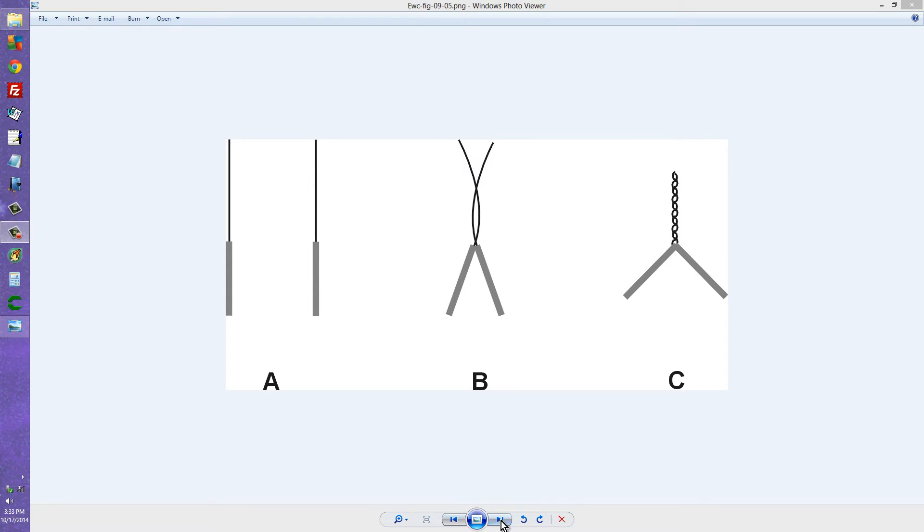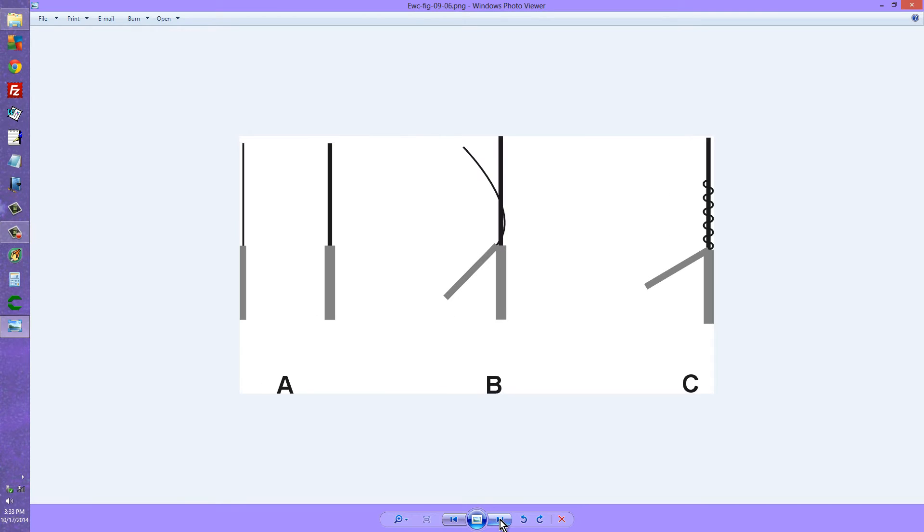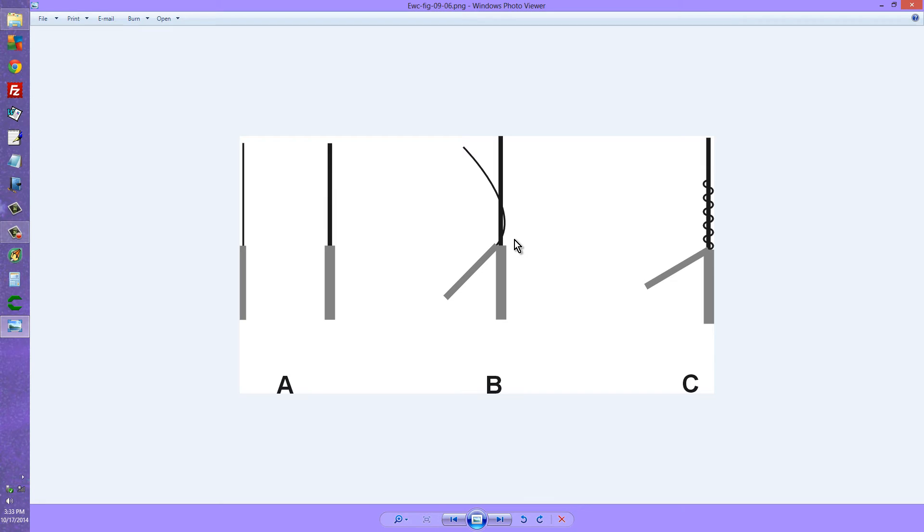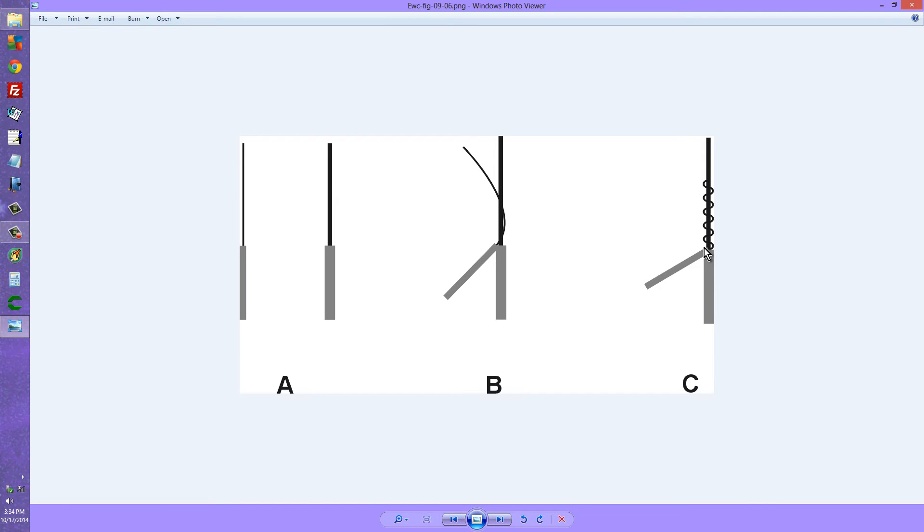If the wires happen to differ in diameter, say you have here AWG number 14 and here AWG number 18 or 20, once again you bring them together with the insulation stripped about an inch off of the ends. Then you wrap the skinnier wire around the fatter one like that so that you end up with something like what you see at C here. Again, of course you can solder it.